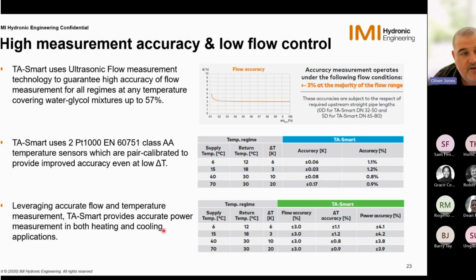And leveraging accurate flow and temperature measurement, the TA Smart also provides accurate power measurement in both heating and cooling applications. So we can see our flow accuracy is at 3%, and our delta T accuracy is roughly between 1.2 and 0.8%. So on average, say about 1%. And then our power accuracy is within 4%. So this is highly accurate from all points of view.